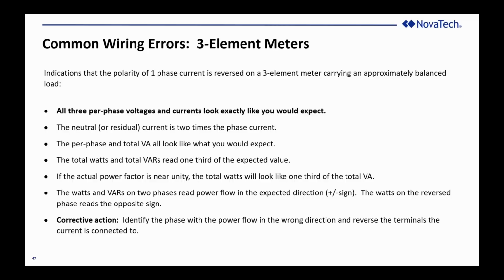Beyond that, the actual power factor is near unity. The watts will look like 1/3 of the total VA. That's a good indicator because that's typically one of the things that you see on a multifunction meter when it scrolls through. The watts and the VARs on the 2 phases read power flow in the expected direction, and the watts on the reversed phase read it in the opposite direction. If you display the per phase watts, you're going to see the sign, and that'll tell you which one to correct.